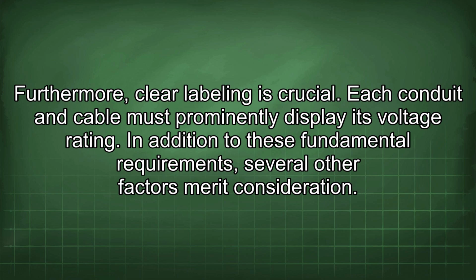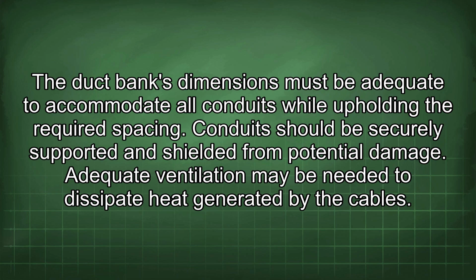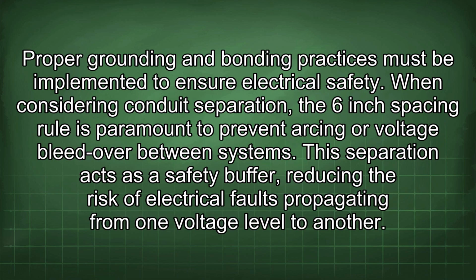In addition to these fundamental requirements, several other factors merit consideration. The duct bank's dimensions must be adequate to accommodate all conduits while upholding the required spacing. Conduit should be securely supported and shielded from potential damage. Adequate ventilation may be needed to dissipate heat generated by the cables. Proper grounding and bonding practices must be implemented to ensure electrical safety.